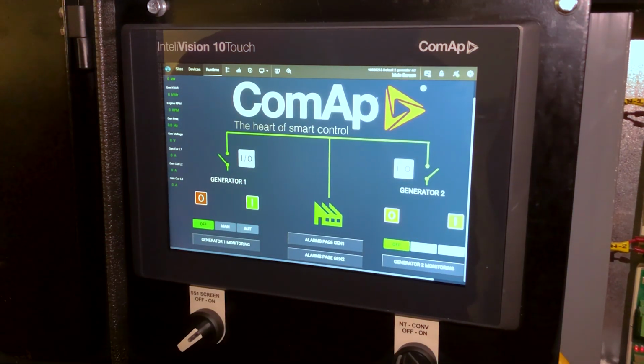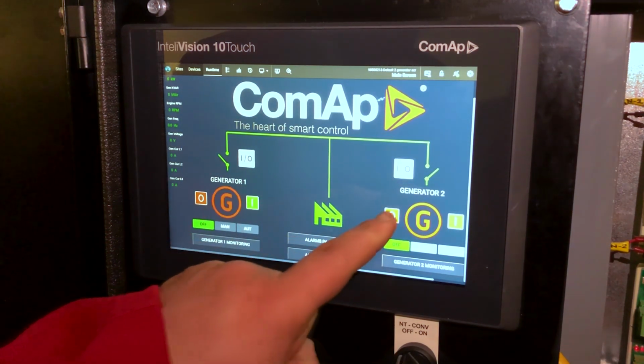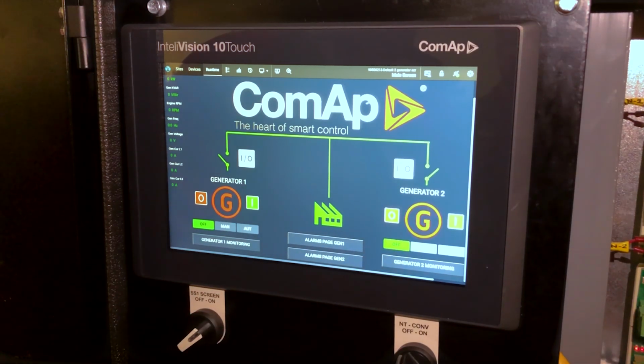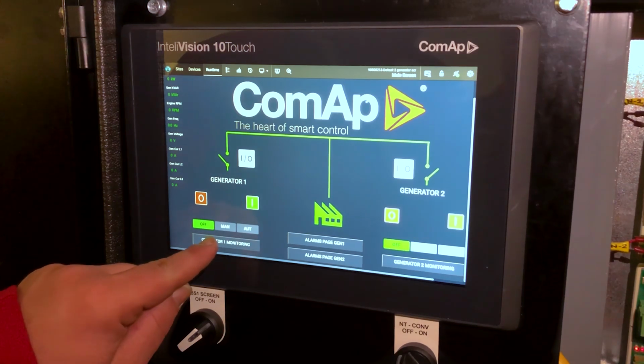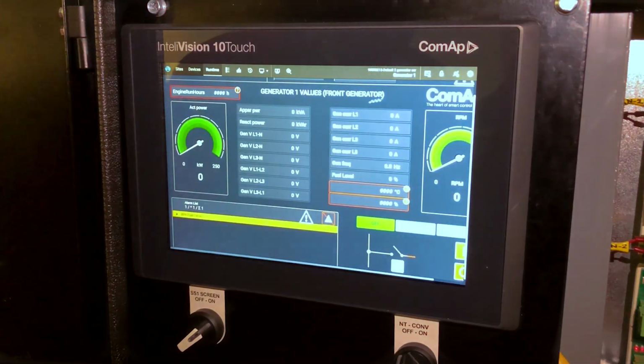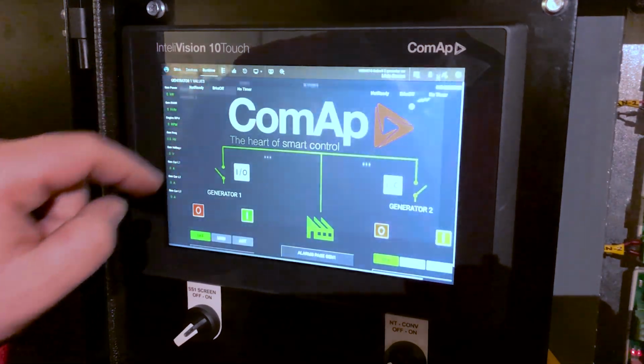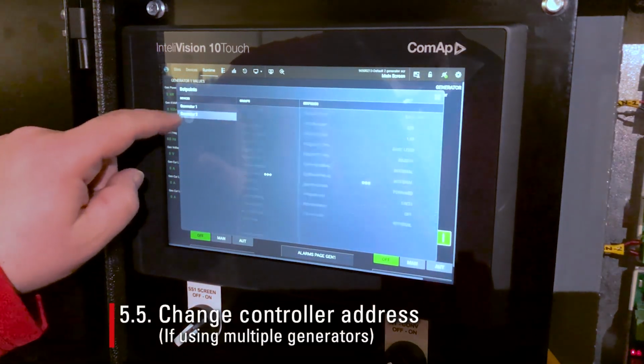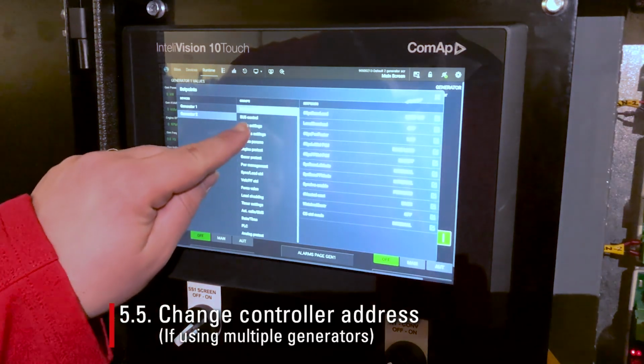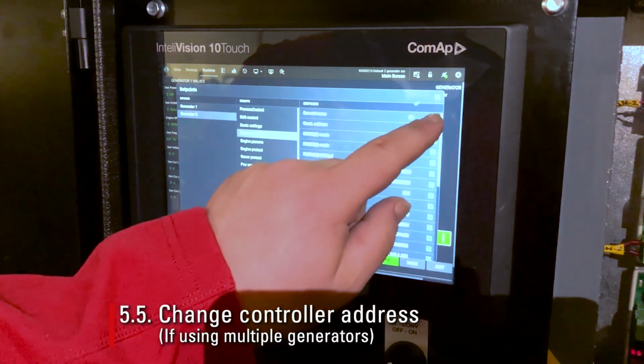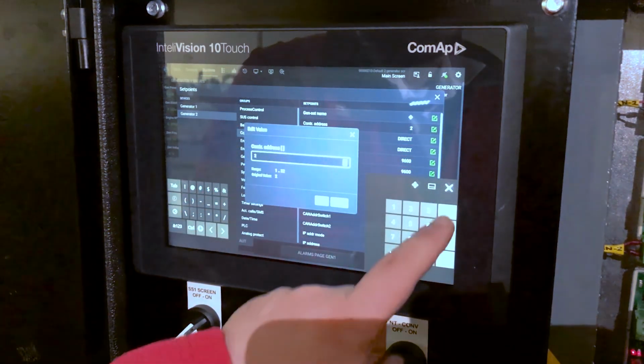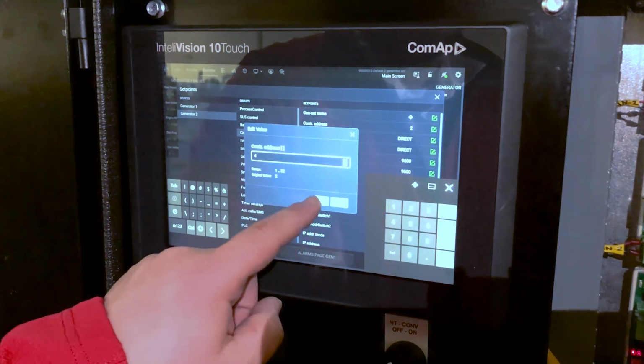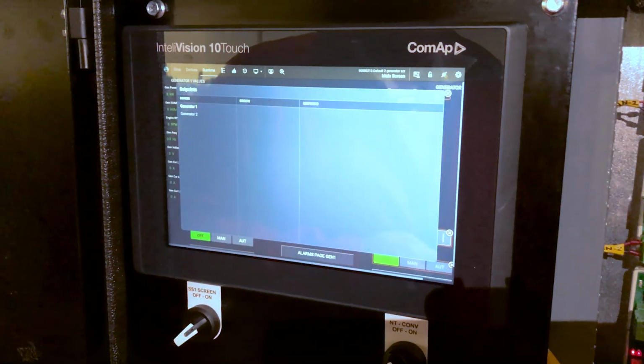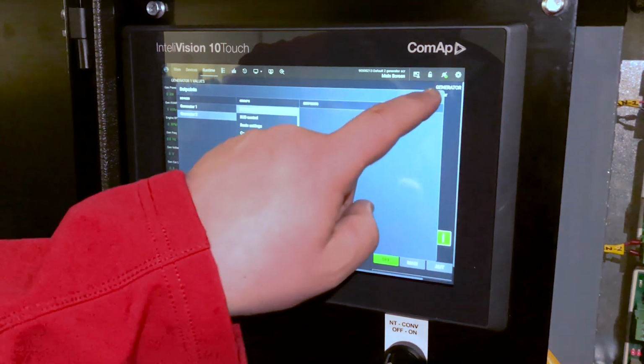On the home screen, we can see generator 1 and generator 2. For a more detailed view of each generator, press the individual generator monitoring button. If you are paralleling more than one twin pack, you'll need to change the controller addresses of the additional gensets. To do this, navigate to Set Points. In a scenario with two twin packs, you will need to change the front generator of the secondary unit to controller address 3 and the rear generator to controller address 4.